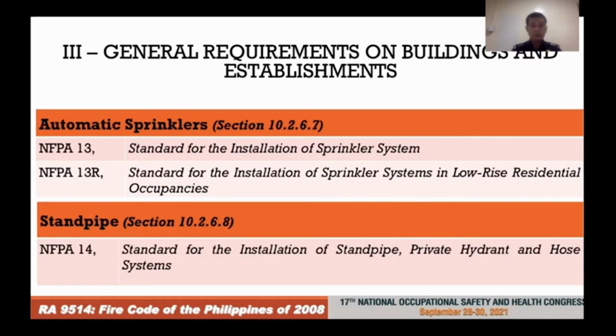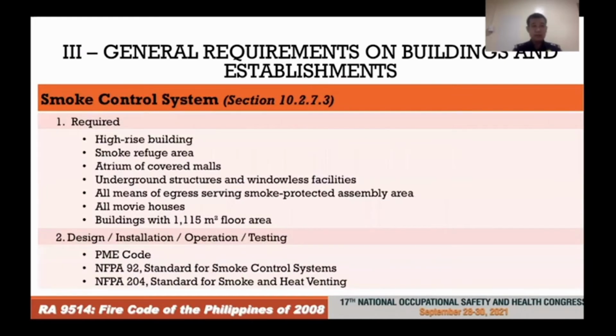Now, another very important requirement is the institutionalization of the requirement for a smoke control system in high-rise buildings, smoke refuge areas, atria of covered malls, underground structures and windowless facilities, all means of egress that are smoke protected, all movie houses, and all other buildings with an area of at least 1,115 square meters. Now, the design, installation, operation, or testing of this smoke control system should be in accordance with the Philippine Mechanical Code or the PME Code, NFPA 92, the standard for smoke control systems, and NFPA 204, the standard for smoke and heat venting.